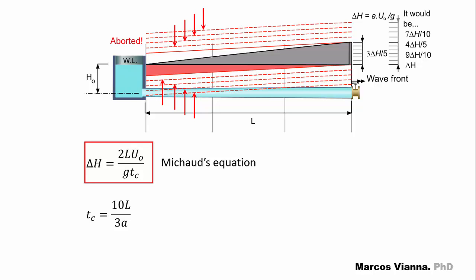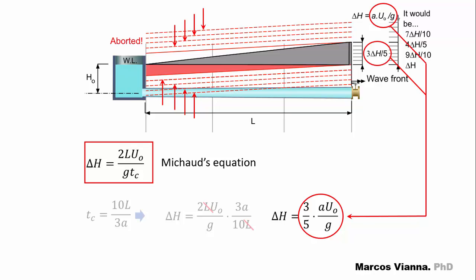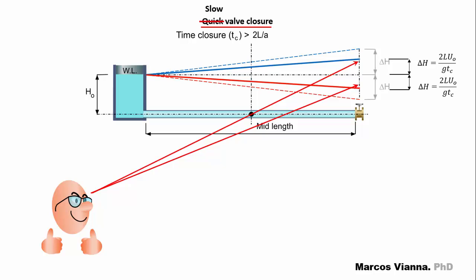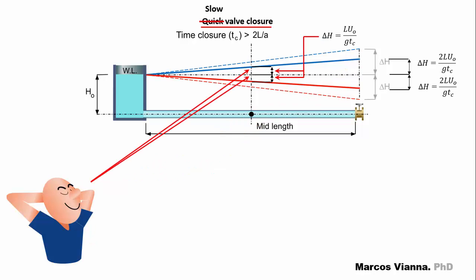As we saw, the closure time of the valve was 10L over 3A. According to Michaud, the pressure variation would be 2LU0 over G times 3A over 10L, or three-fifths AU0 over G — which is the value that we found. To make it clear: if we close the valve in a time equal to or smaller than the reflection time of the pipe, the pressure variation at the valve will be AU0 over G. If we close the valve in a time greater than the reflection time, the pressure variation will be smaller. If we assume the valve closes linearly, the pressure variation at mid-length will be equal to LU0 over GTC.